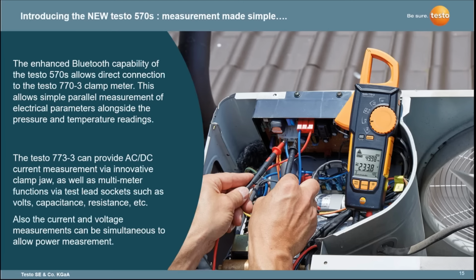So the 770-3 can provide AC and DC current measurement via its fairly innovative clamp jaw. It's a parallel jaw, which means you can get into much tighter cabling rather than a jaw that hinges sideways. The device is also a fully featured multimeter, so via the jack connections at the bottom, you can use test leads to have it as a voltmeter for AC and DC use, and also you can do capacitance, resistance testing, continuity testing, and quite uniquely, you can also perform both a simultaneous current and voltage measurement, and actually the device will then give you power measurement as well. So it's a really competent device for doing electrical testing around the systems as well.